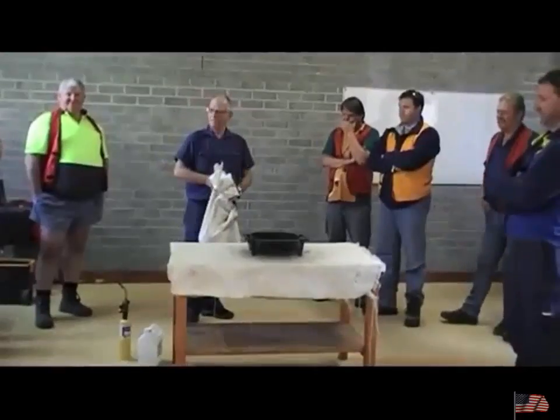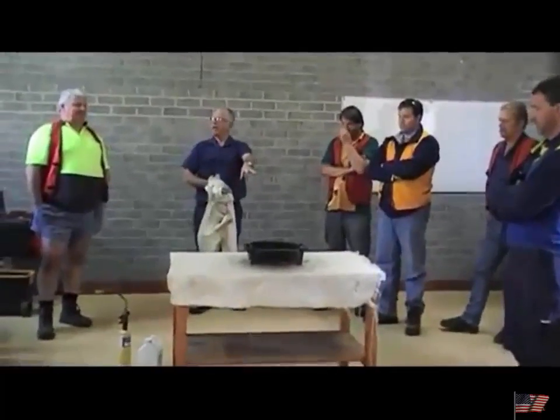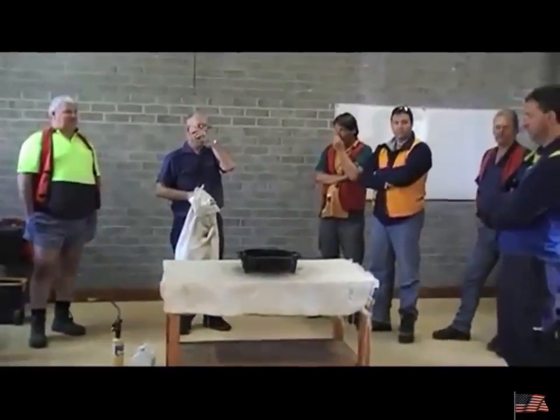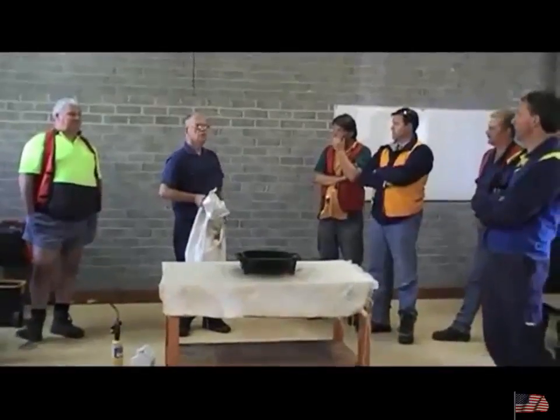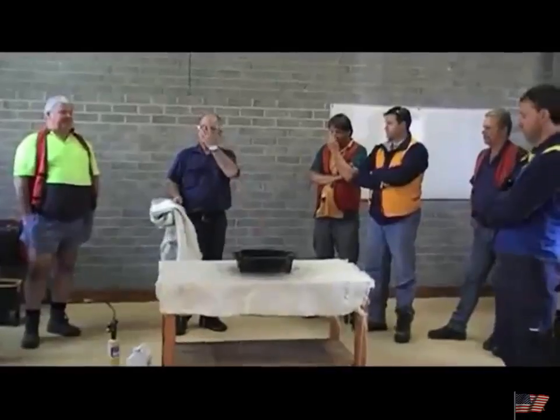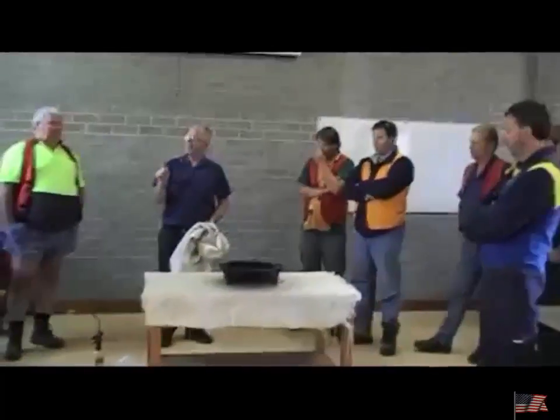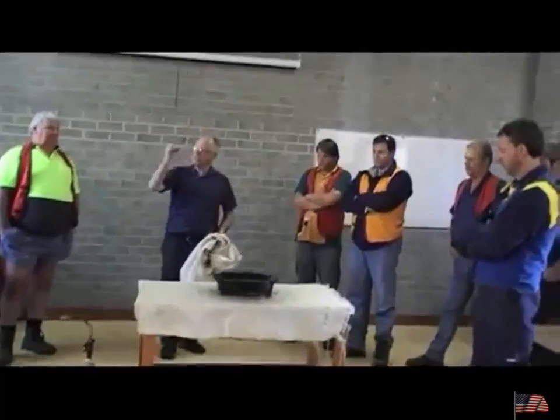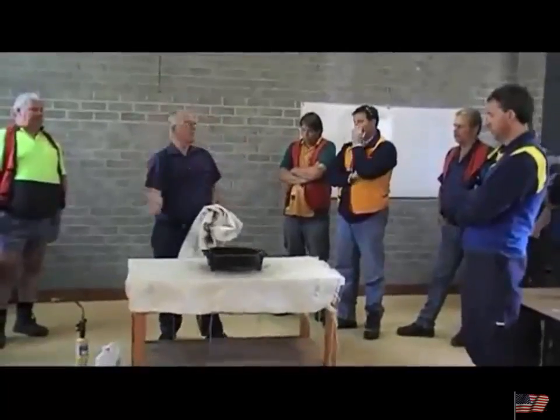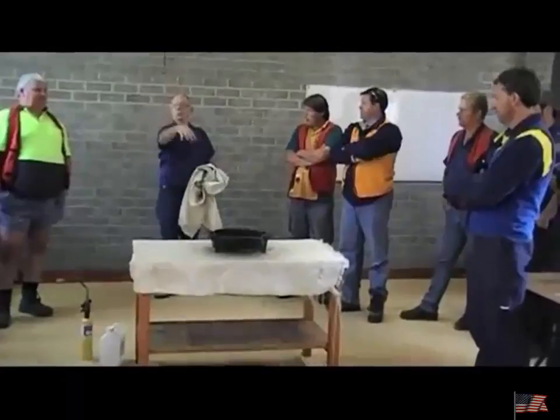You don't. Now, can I use dry chemical powder on that that's on fire? What do you reckon? Which extinguisher? There's only one. A, B, or B, it doesn't really matter. Yes, I could. What's the biggest problem with me doing that? Blowing it out of there. Blowing it out of there, because it comes out of that nozzle in a very small hole, doesn't it? And all that pressure is going to blow it everywhere. So we can't really do that unless you stand back and sort of let it fall down.